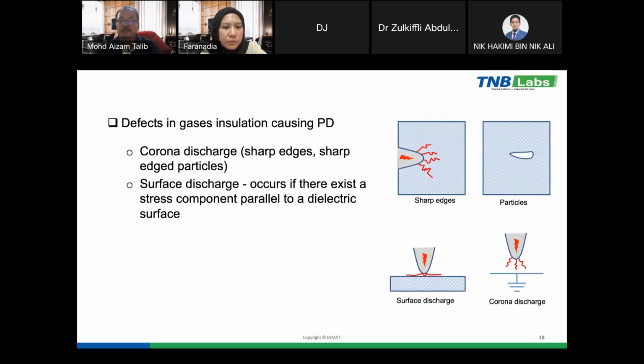And then for gases, normally the partial discharge is due to corona discharge when we have sharp edges or when we have a particle. Sometimes we have contamination, where there is a presence of particles, and these particles will bounce around in the GIS, for example, and then create partial discharge. The others are corona discharge and surface discharge.